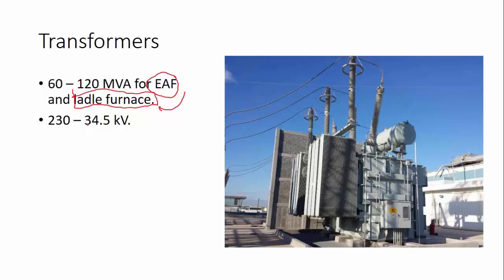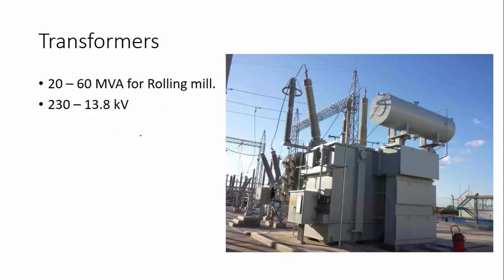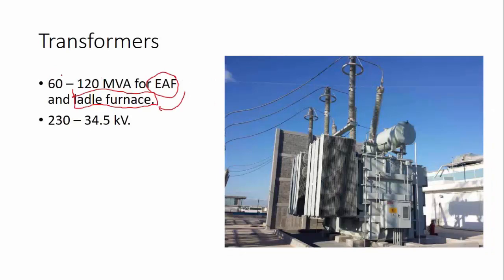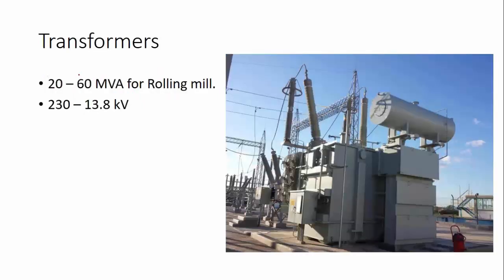These transformers are typically 230 to 34.5 kilovolts. This is a very typical arrangement in an electric arc furnace facility. Now, next to it, we'll have a much smaller transformer, which is 20 to 60 MVA. The electric arc furnace transformer typically goes from 60 to 120 MVA. It's very big. This one is much smaller, and it's for the rolling mill. It's just for the machines that will treat the already molten steel, the rolls of steel, rolling it to the desired width. Normally, this part of the plant is handled at 13.8 kilovolts, at least here in Mexico.